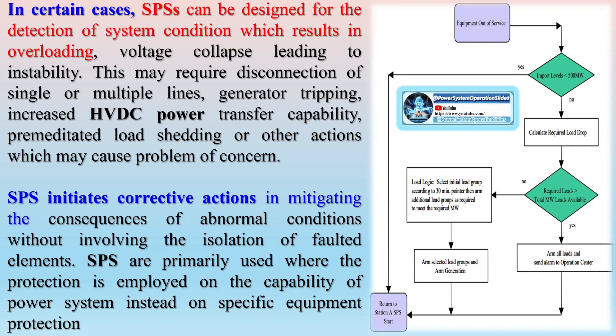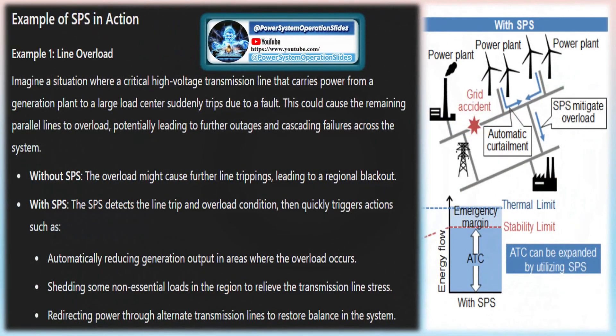Frequency instability occurs when power system frequency varies beyond the operating limits. Corrective actions include generator tripping, rapid generation reduction through fast valving or water diversion, control of HVDC power transfer, load shedding, controlled opening of interconnection to neighboring systems to prevent spreading of disturbance, and controlled islanding of the local system into separate areas with matching generation and load.